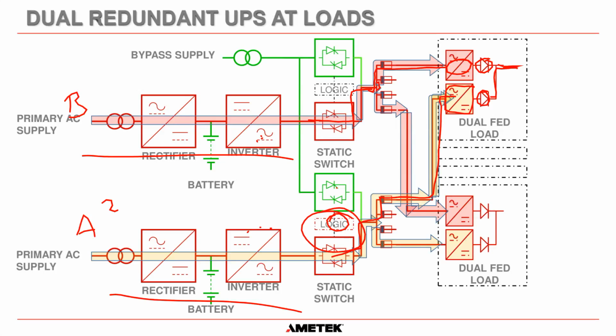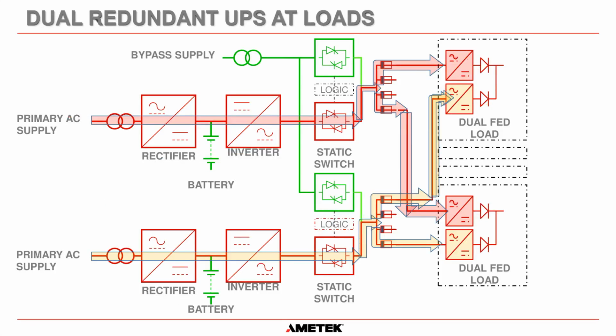In truth, you could have a 20 kVA UPS here from one manufacturer and a 20 kVA UPS here from another manufacturer, if you wanted to. It doesn't make sense because you want all the spare parts and everything to be the same, but you could, in theory, do that. The only issue with this system here is whenever you add load onto the output of a dual redundant UPS connected at load, you have to remember that you always have to connect both UPSs to that load to add that redundancy in.